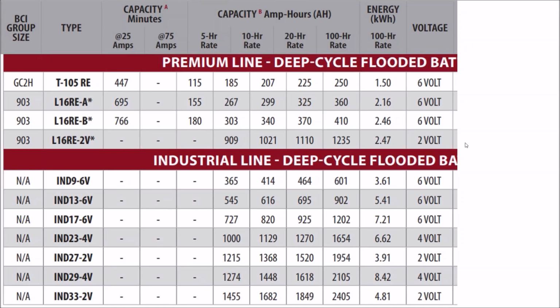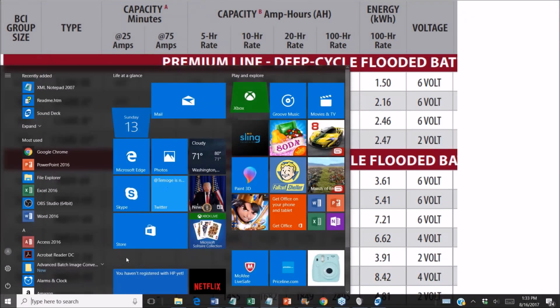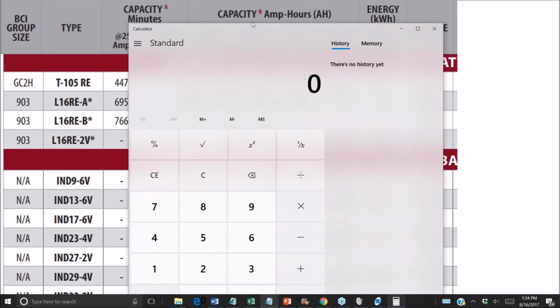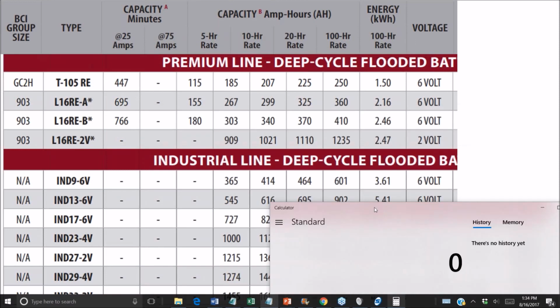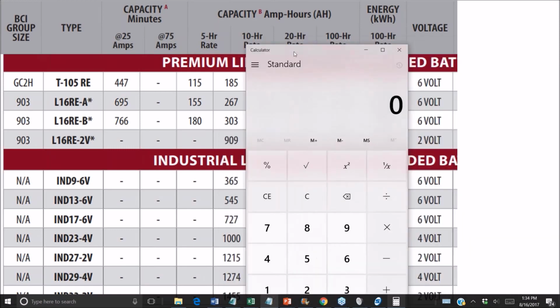Remember, we need a 122 kilowatt hour battery bank. One problem I ran into: based on the PV Watts production, we need about a 22 kilowatt array. Looking at the production of a 22 kilowatt solar array, subtracting the house's consumption, what we need is a 122 kilowatt hour battery bank, since that's as large a battery as we need for lead acid so we're not completely draining the batteries, and the system would work through typical storm cycles without a generator. But we'll have a generator anyway just to protect it. Don't worry, though, you don't need a generator. This customer specifically requested he not need to worry about a generator working or not — he's trying to be off grid to be free, and doesn't want to become trapped by worrying about his system's functionality.